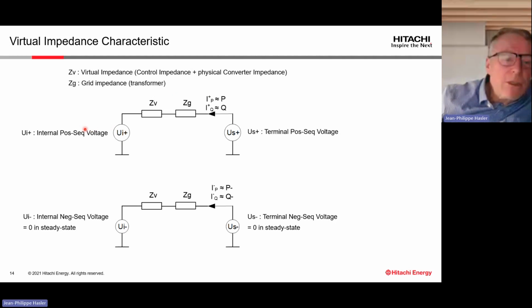For the positive sequence we also have to define the internal voltage, which will be mainly driven by relatively slow power control or inertia control. For the negative sequence we have exactly the same impedance, and the internal voltage is normally set to 0. That means the current is only defined by the negative sequence perturbation divided by the total impedance. No other control should interact with this current.